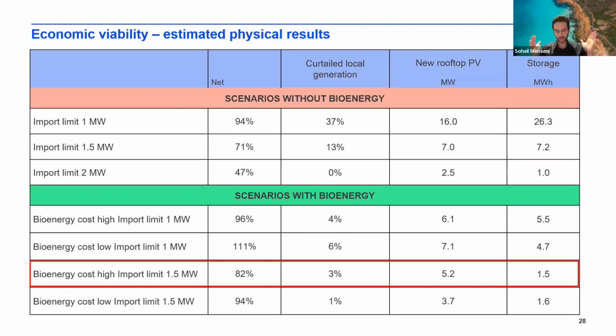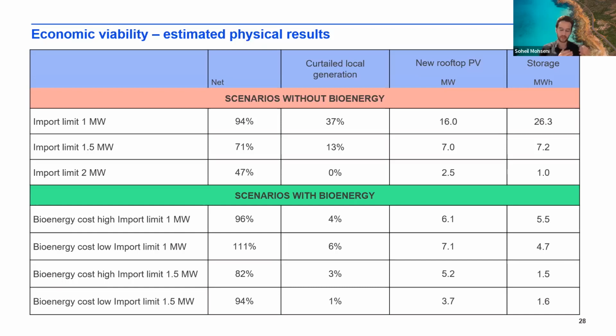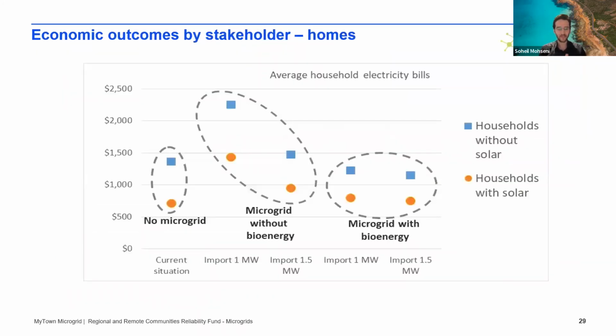But for all of the cases with bioenergy, generally the curtailment is really low. We're looking at curtailment between 1% and 6%, whereas we're looking at curtailment between 13% and 37% in the ones without bioenergy, with import limits of 1 to 1.5 megawatts, which gives us reasonable amounts of local supply. Next slide, please.